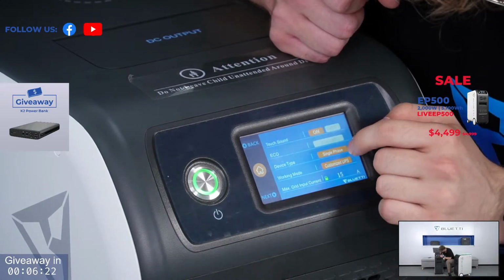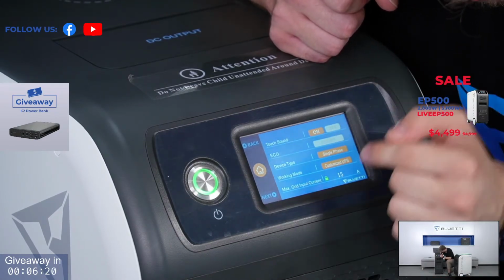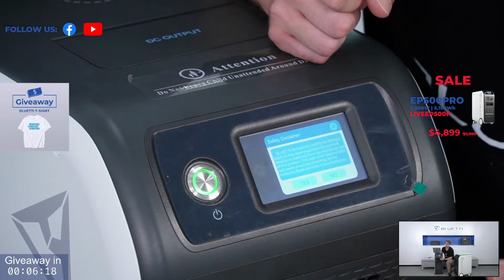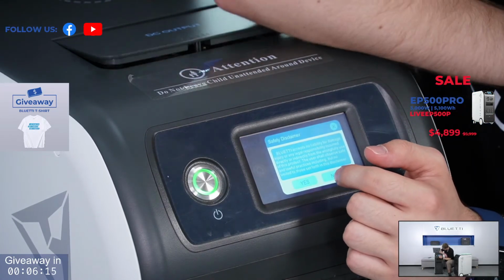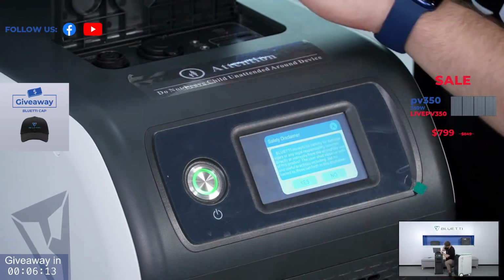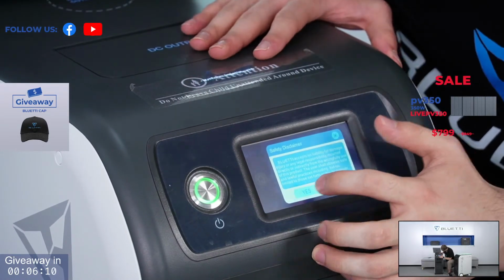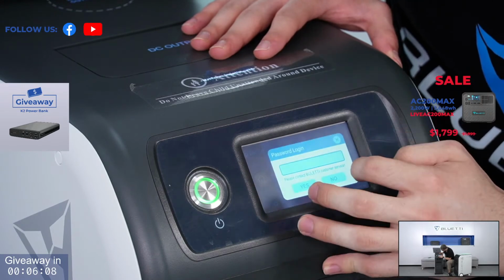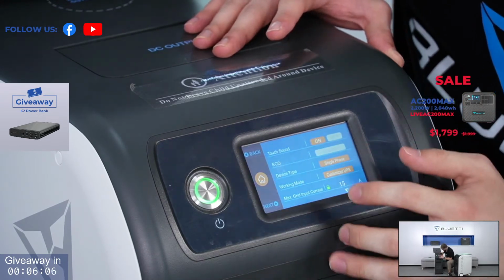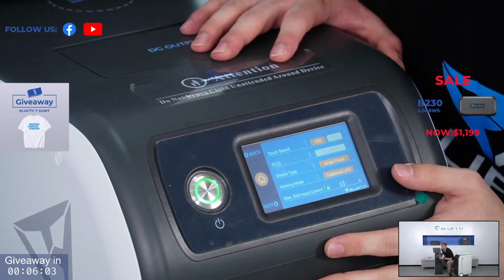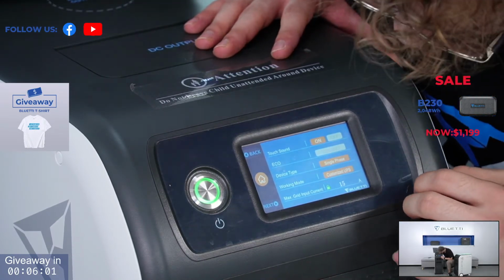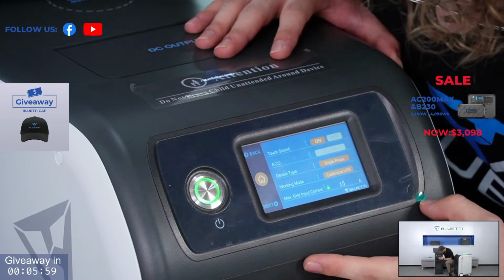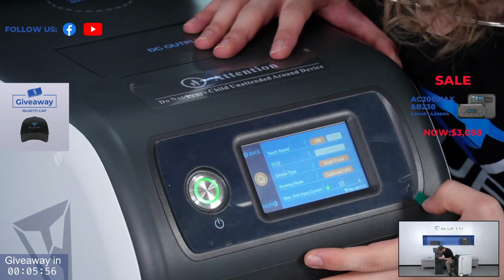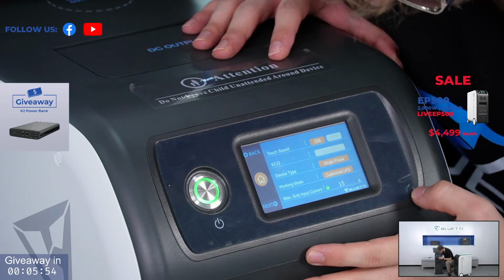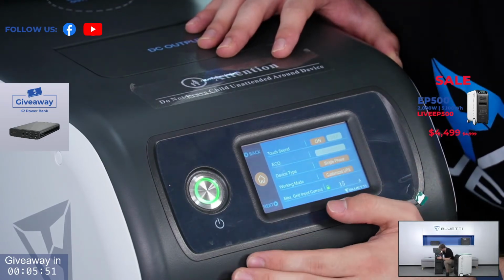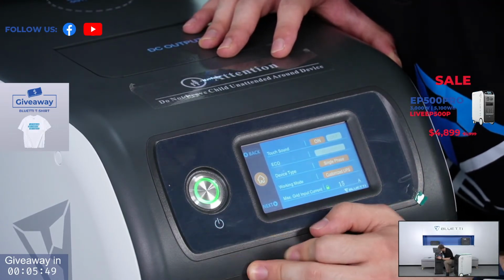Maximum grid input current, 15 amps is the max by default, but if you want more you can set it here. You need a password though - you'd want to request it from BLUETTI customer service if you absolutely need to max the amperage. By default it's 15 amps. If you need more, contact BLUETTI support, but we don't recommend maxing the amperage unless you absolutely need it and have the knowledge and expertise to do that.